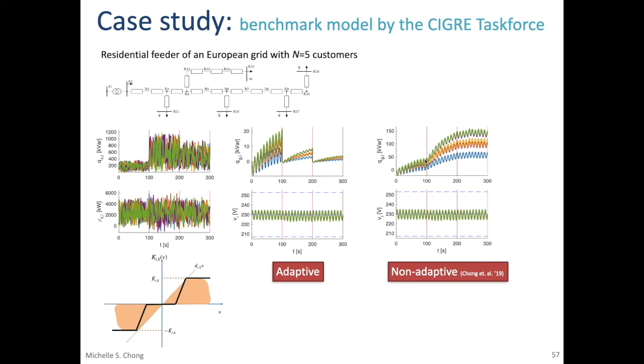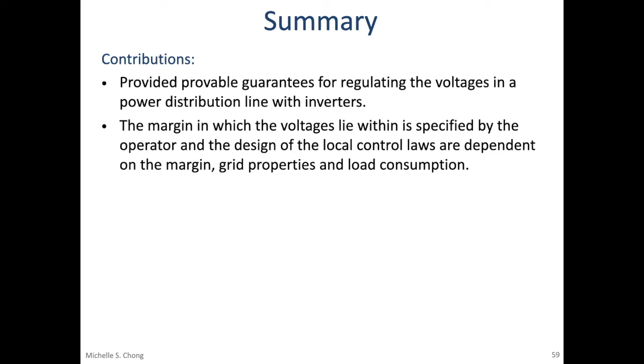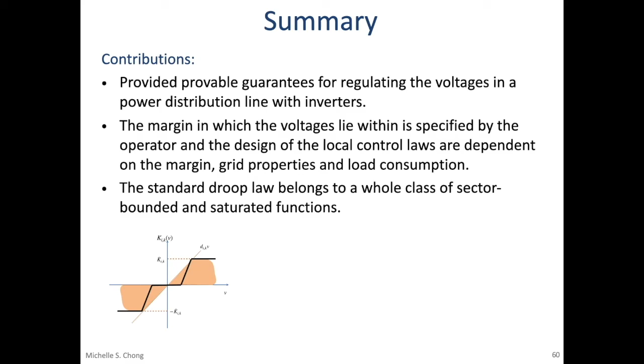To summarize, we have provided a guarantee for voltage regulation in a power distribution network in a line configuration. Our proposed method allows the operator to specify the margin of error, and the local controllers are then designed to meet this criteria. We showed that a whole class of functions can achieve this task, which extends beyond the standard droop law used in the literature.